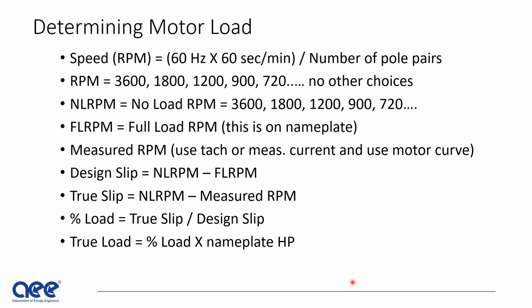So the design slip is going to be the no load RPM minus the full load RPM. The true slip is the no load RPM minus the measured RPM. The percent load is true slip divided by design slip. So the true load is going to be percent load times the nameplate.